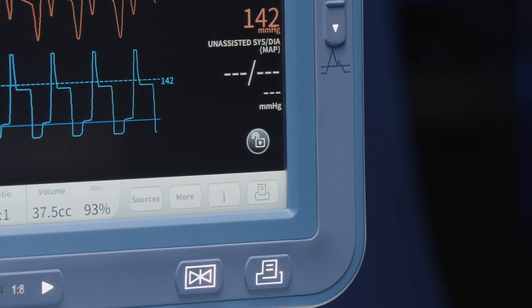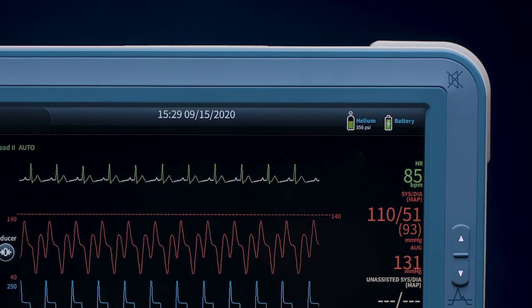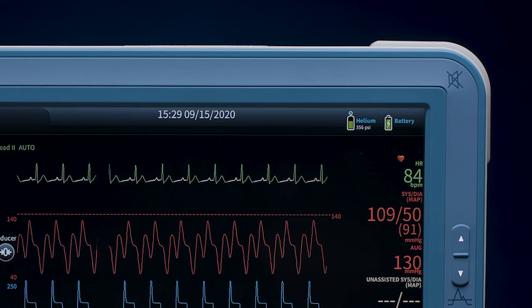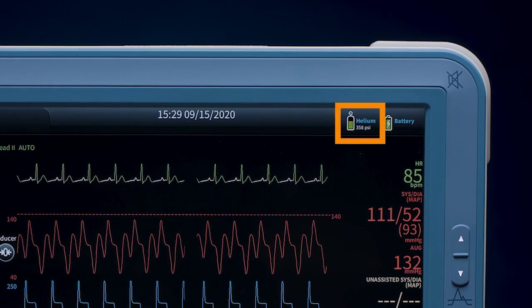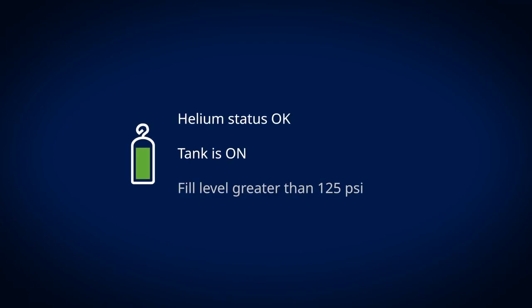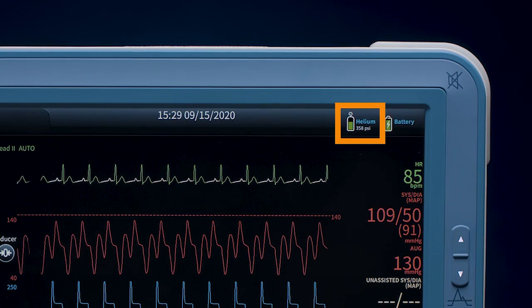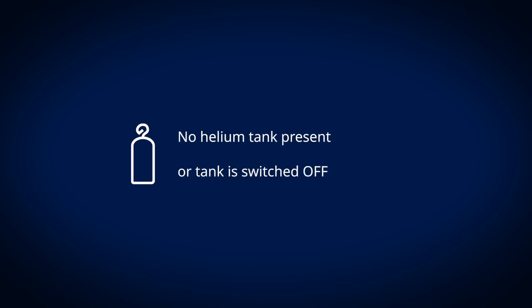The unlocked icon displays. The helium supply and AC power and battery indicators are located in the upper right-hand corner of the control display. A green helium supply icon indicates the helium status is okay, the tank is on, and the fill level is greater than 125 psi. The psi level will also be seen on the screen next to the helium supply icon. A red helium supply icon indicates that the helium supply level is less than 125 psi, while a black icon indicates that there is no helium tank or the tank is off.